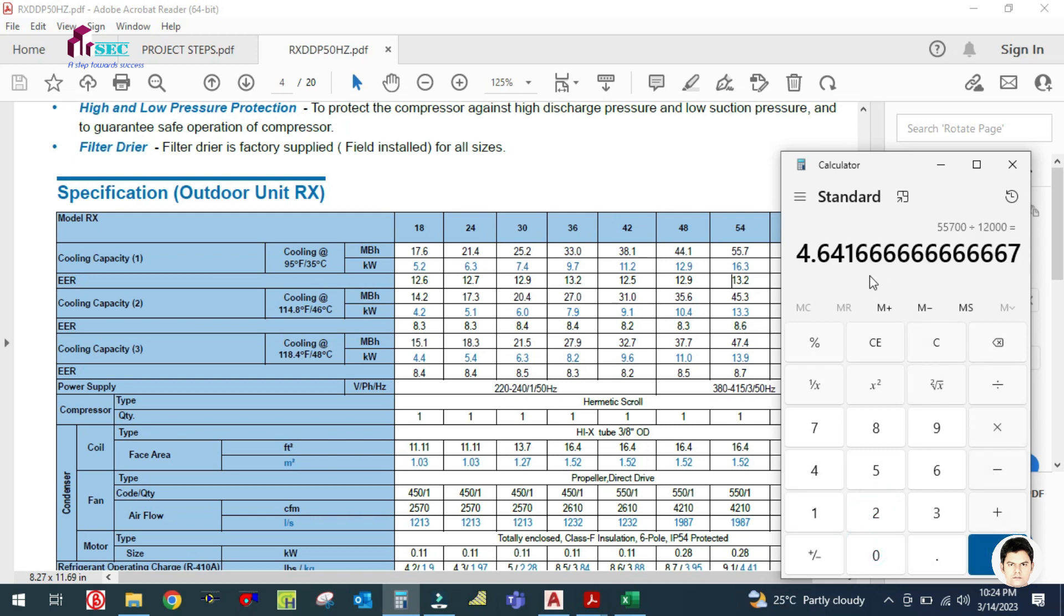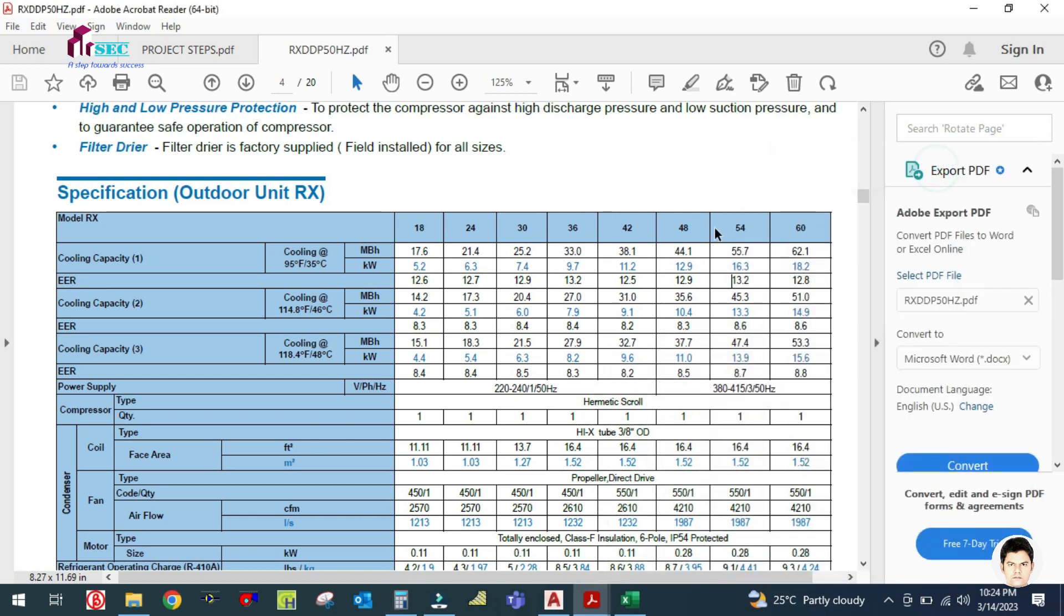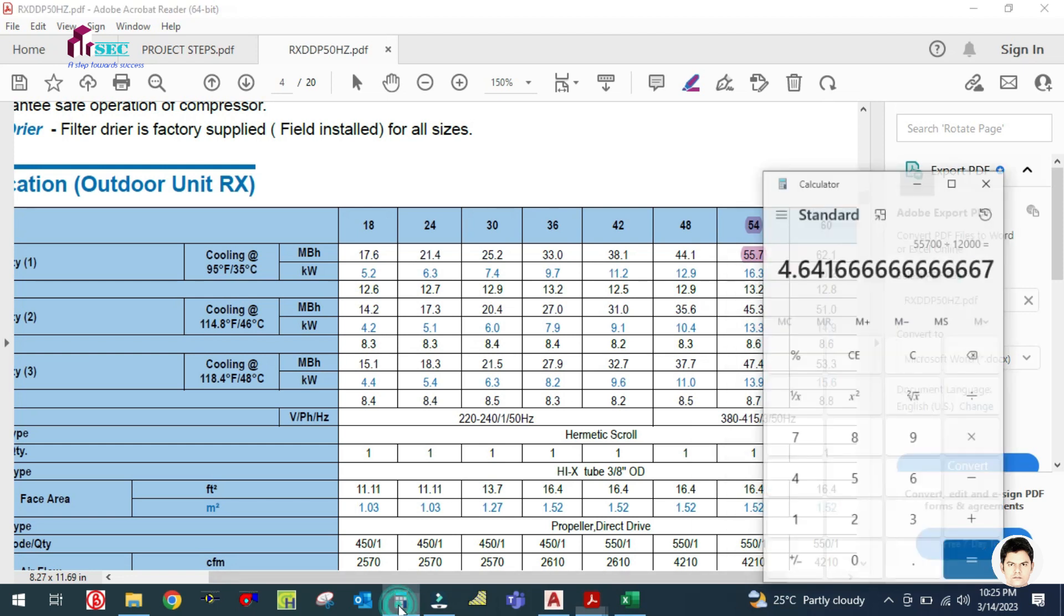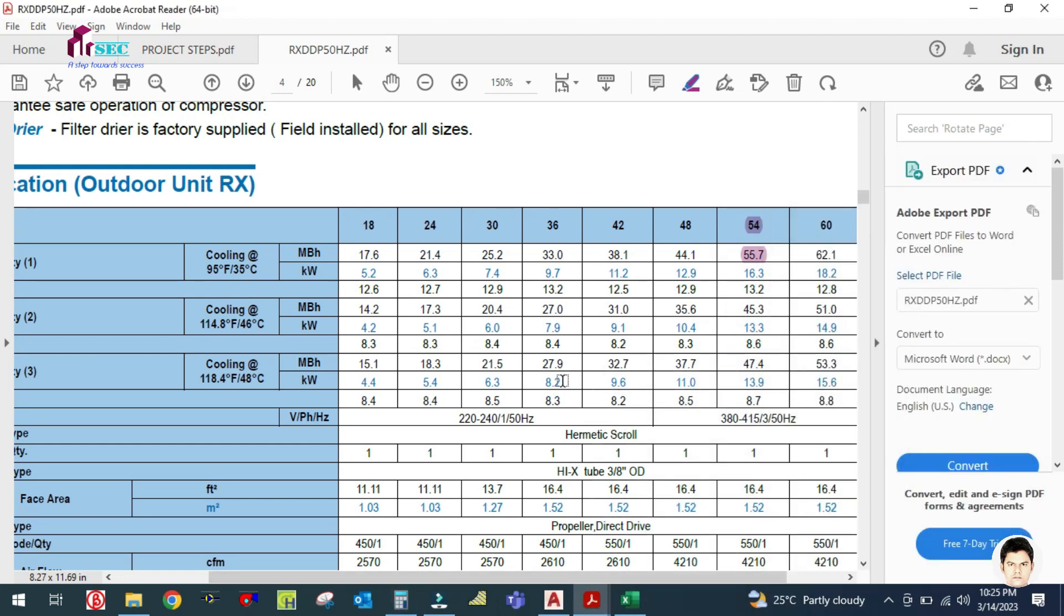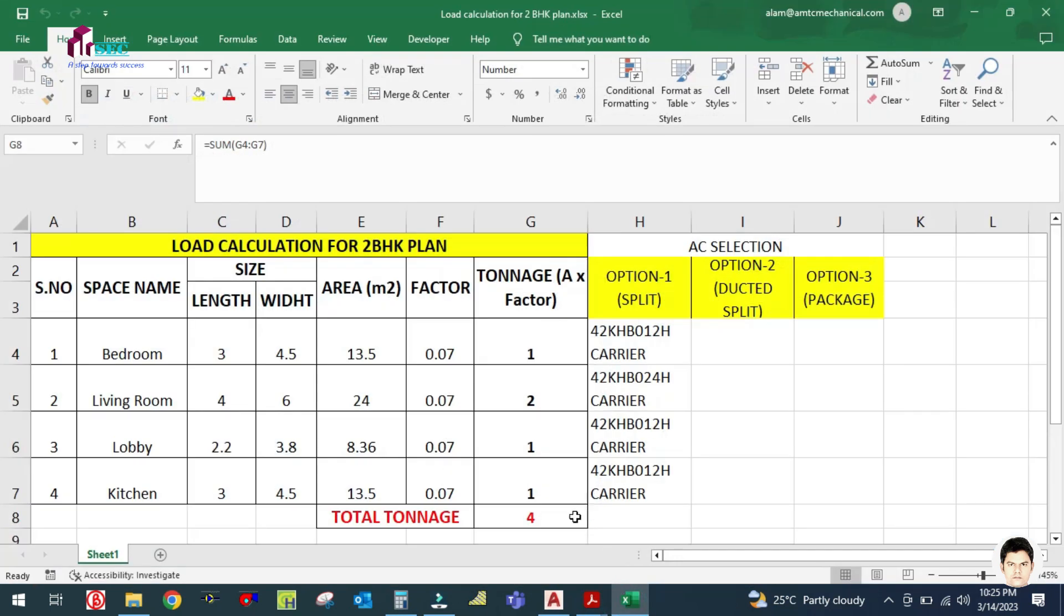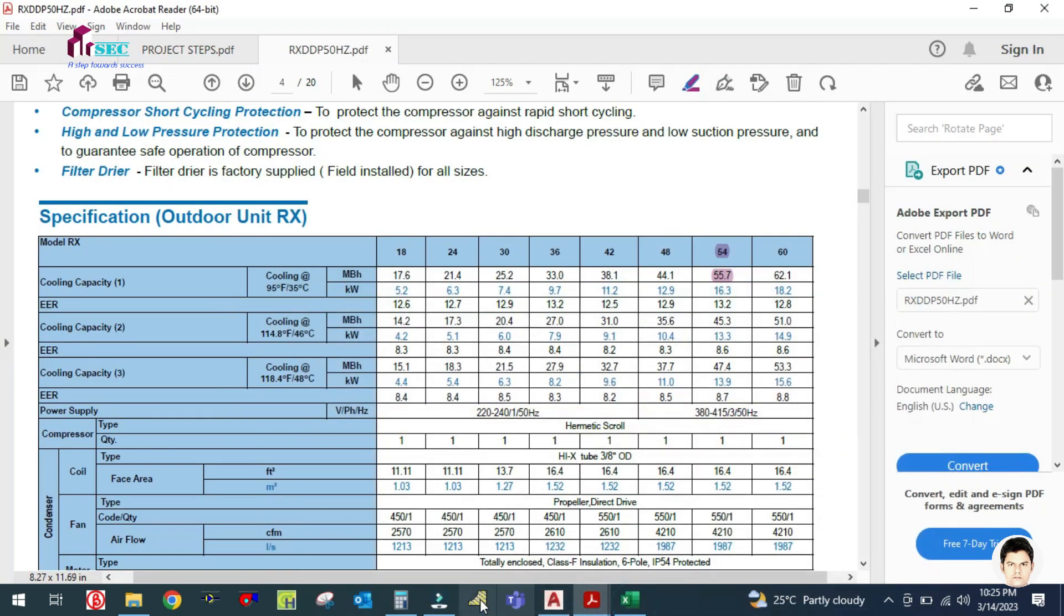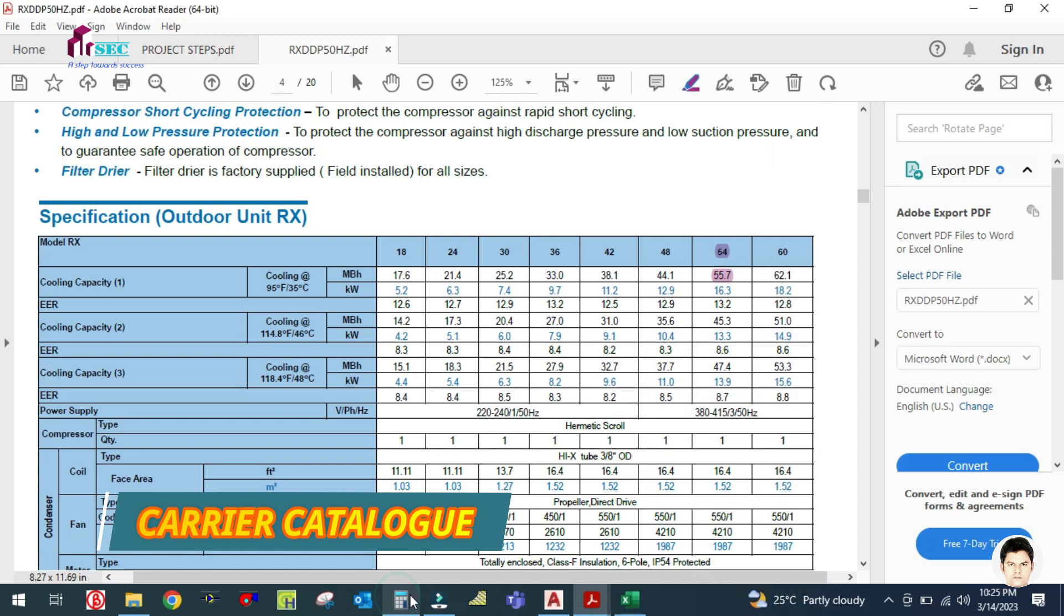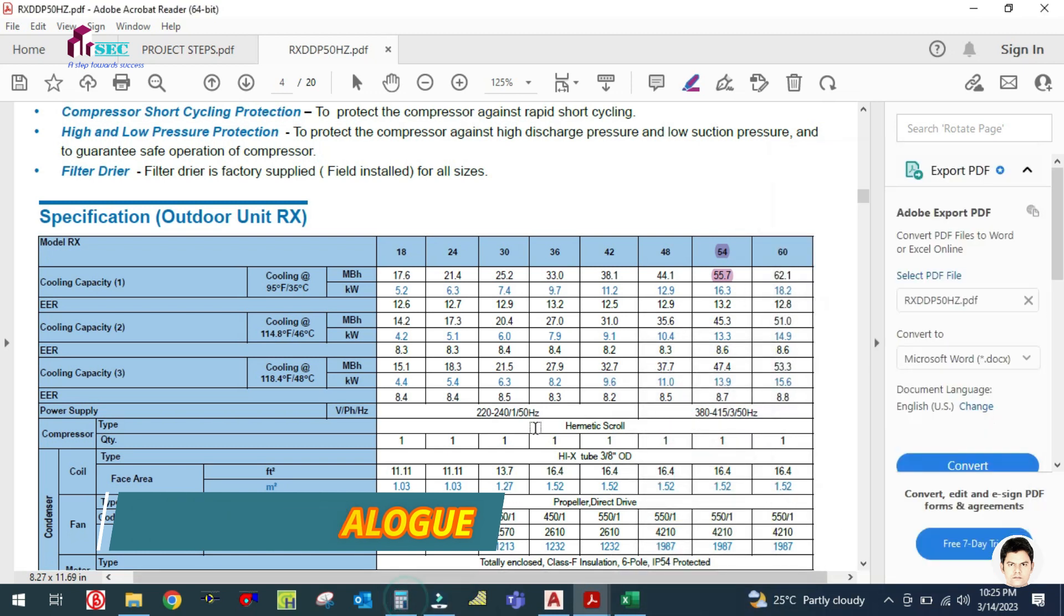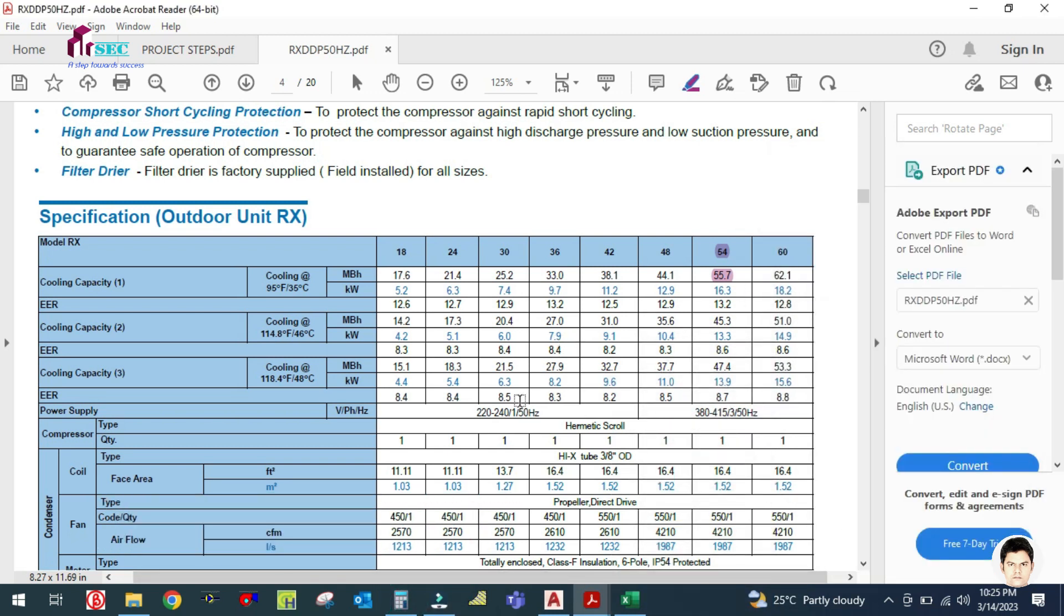So we can select this AC. This model, the 54 model. The capacity of this model is 55.7 MBH, which is 4.6 tons, and our requirement is 4 tons. So we have selected the 4.6 ton, which is safe side.